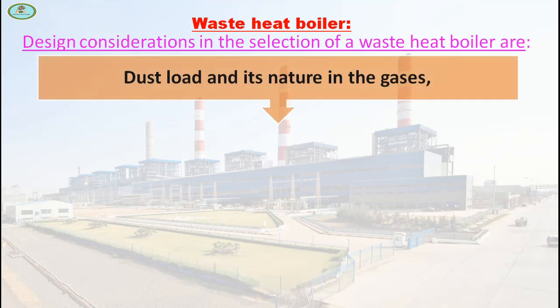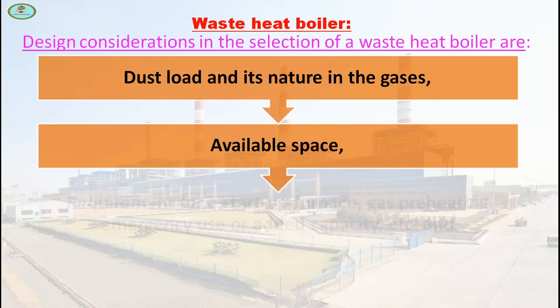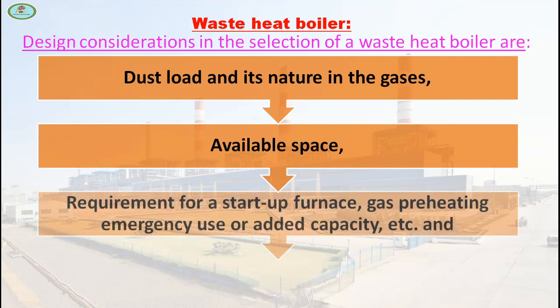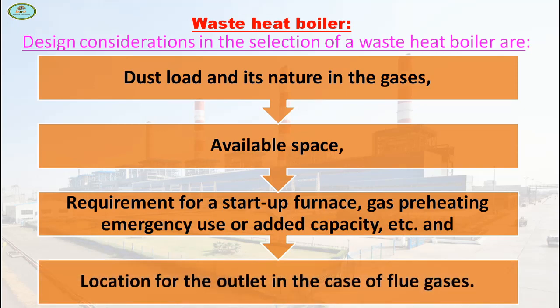Dust load and its nature in the gases. Available space. Requirement for a start-up furnace. Gas pre-heating, emergency use, or added capacity, etc. And location for the outlet in the case of flue gases.